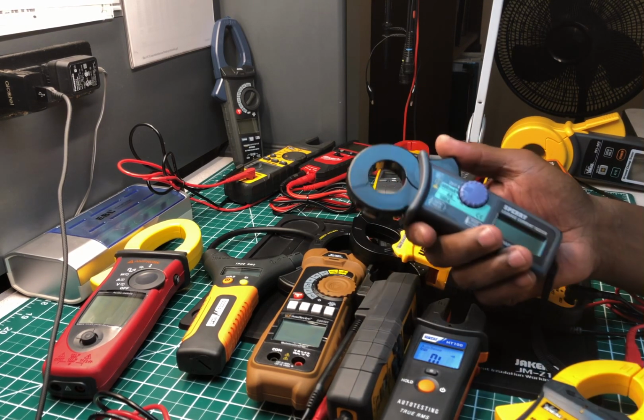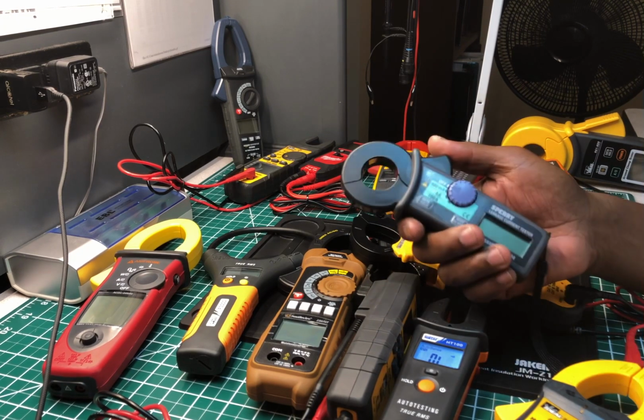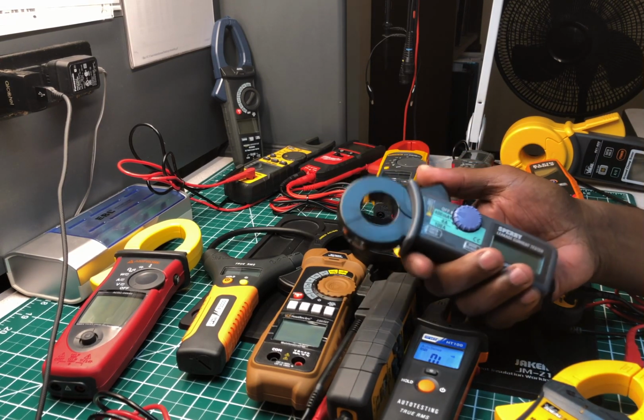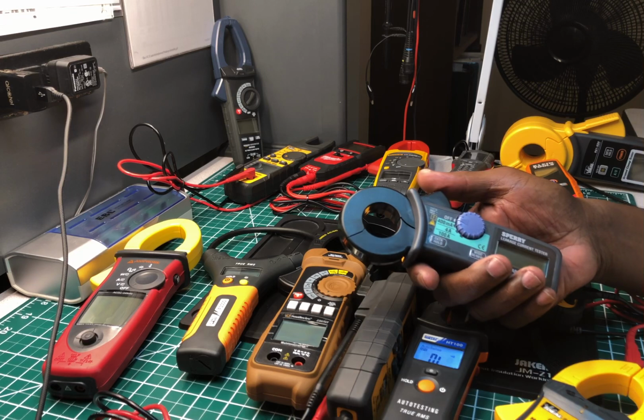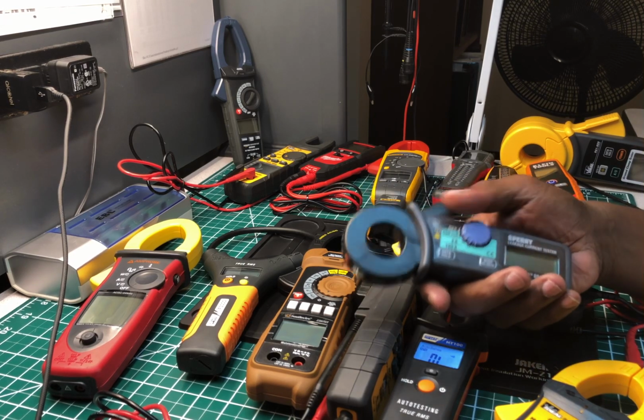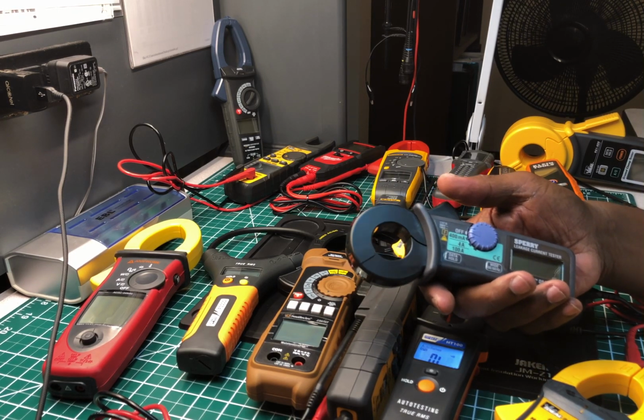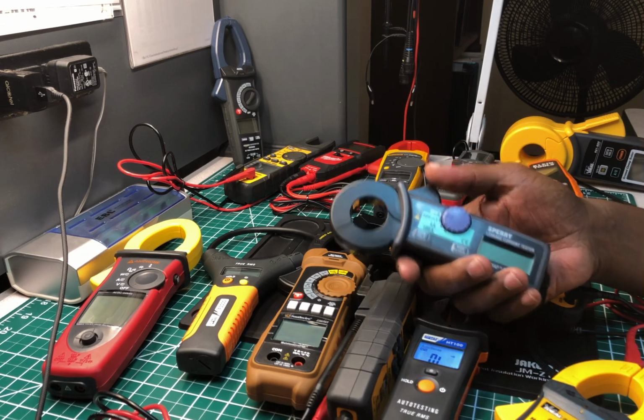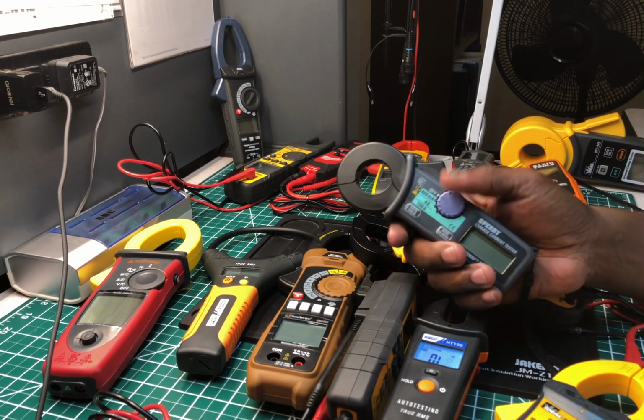Every now and then it does intermittent tripping. So what you do is clamp this around the neutral and the hot, and you'll see how much leakage is causing your breaker to trip.